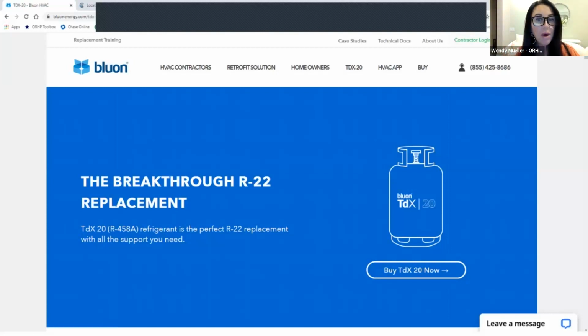Can you just add Bluon if the system needs it, or do you have to replace all the R22? You have to replace all of it. It is a drop-in, meaning you have to take out the remaining R22 and then add the Bluon, because it's like oil and water. Anytime you change these chemical components, they don't mix, so you have to have one or the other. So if it would take 10 pounds of Bluon in a system, you can't add 4 pounds of Bluon with 6 pounds left of Freon or R22.